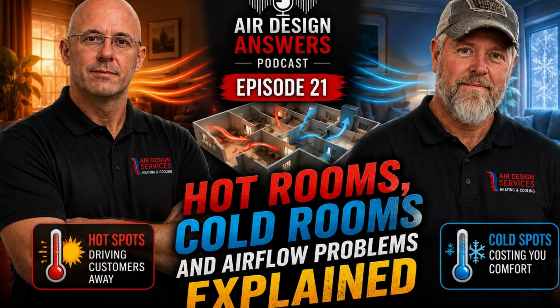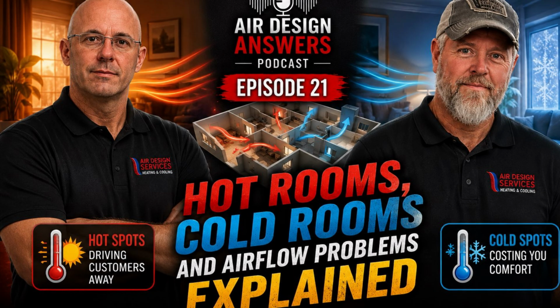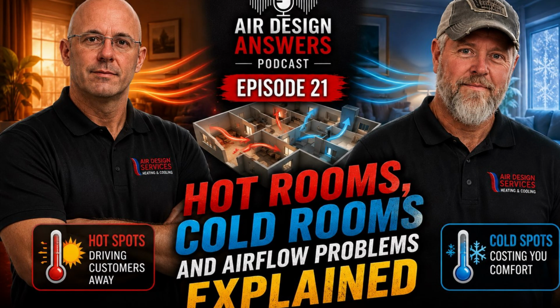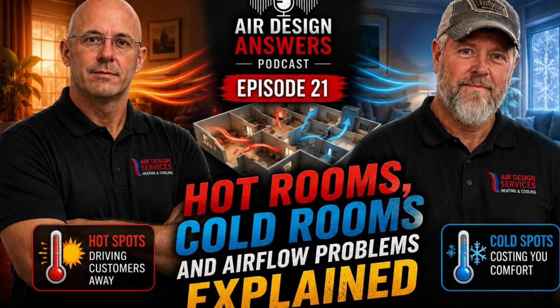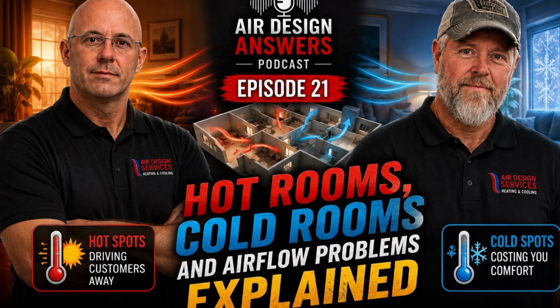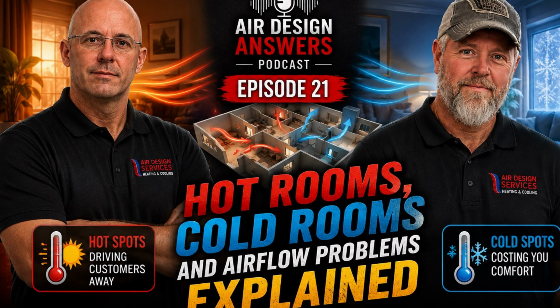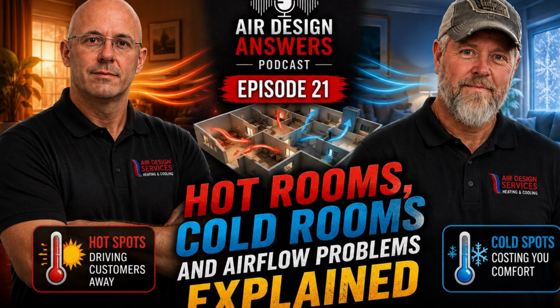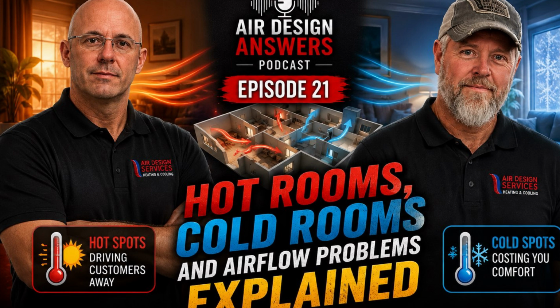Sun exposure plays a bigger role than many people realize. Two rooms can be the exact same size, have the exact same vents, and receive the exact same amount of airflow. But if one room has large west-facing windows, it can feel completely different. Another thing we see a lot is homeowners closing vents in rooms they're not using. That's a big one. People think they're helping the system. They close vents in guest rooms or spare bedrooms because they assume that extra air will be redirected elsewhere. Unfortunately, HVAC systems don't really work that way.